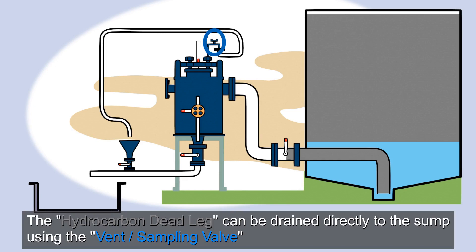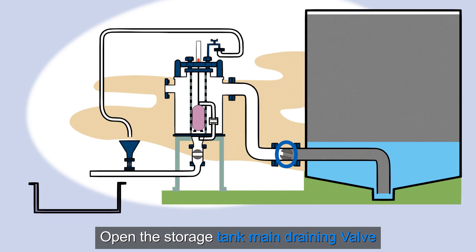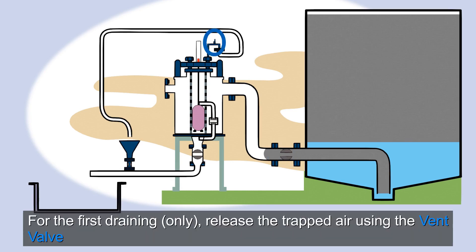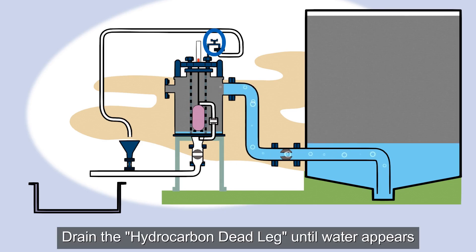The hydrocarbon dead leg can be drained directly to the sump using the vent sampling valve. Open the storage tank main draining valve. For the first draining only, release the trapped air using the vent valve. Drain the hydrocarbon dead leg until water appears.